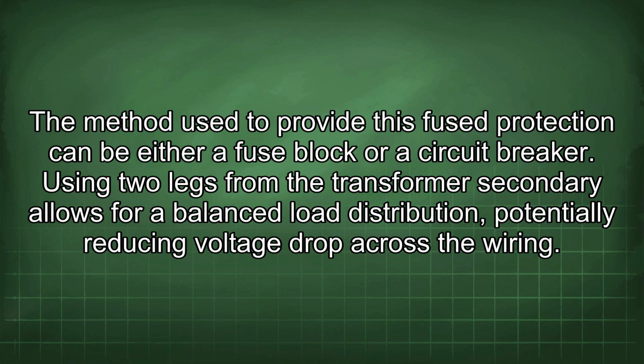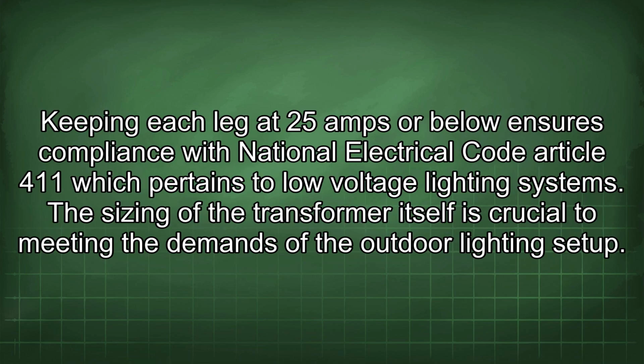Using 2 legs from the transformer secondary allows for a balanced load distribution, potentially reducing voltage drop across the wiring. Keeping each leg at 25 amps or below ensures compliance with National Electrical Code Article 411, which pertains to low-voltage lighting systems. The sizing of the transformer itself is crucial to meeting the demands of the outdoor lighting setup.